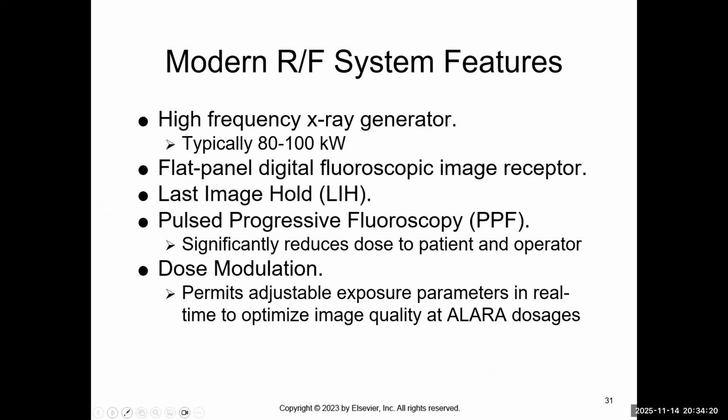All right, our modern fluoro units or rad fluoro units, we do have what we call a high frequency generator, so very efficient pulse generator. It usually or can have that flat panel detector versus the image intensifier. They are capable of last image hold, meaning after I take an image, it holds the very last one.